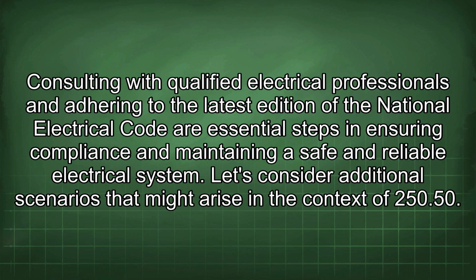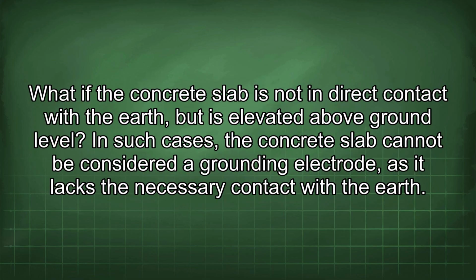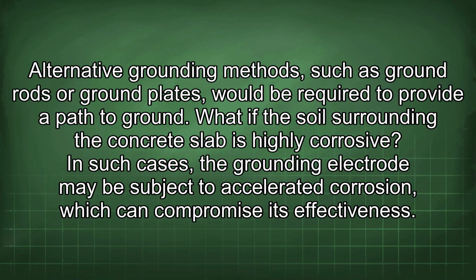Let's consider additional scenarios that might arise in the context of 250.50. What if the concrete slab is not in direct contact with the earth, but is elevated above ground level? In such cases, the concrete slab cannot be considered a grounding electrode, as it lacks the necessary contact with the earth. Alternative grounding methods, such as ground rods or ground plates, would be required to provide a path to ground.